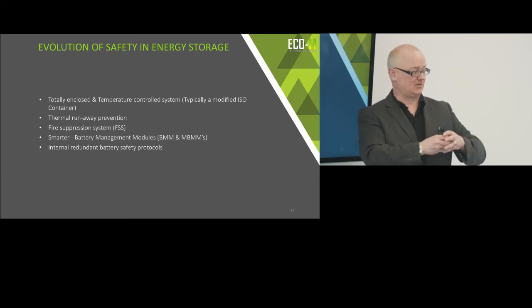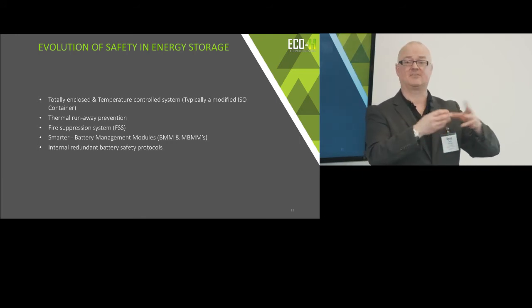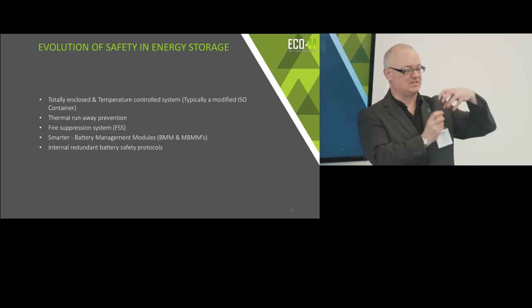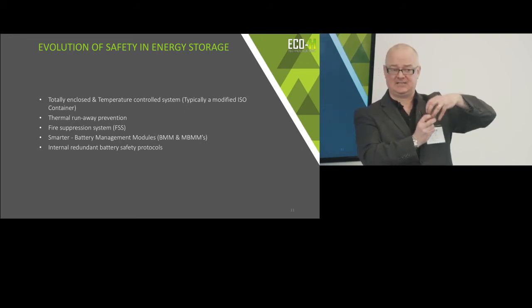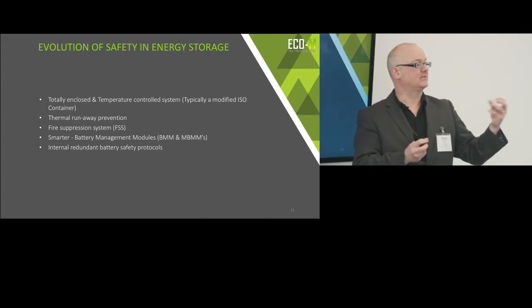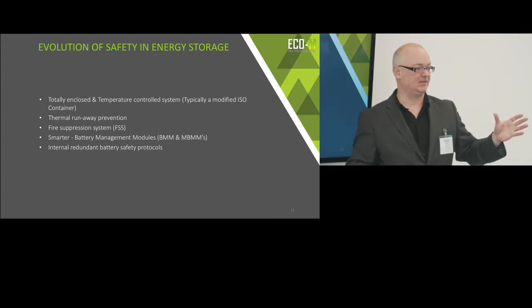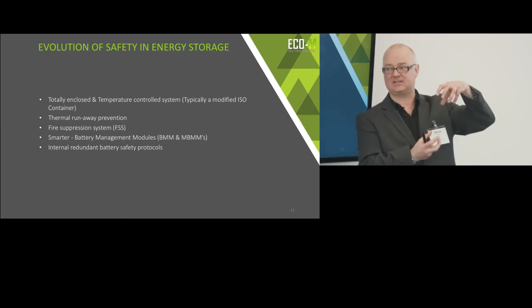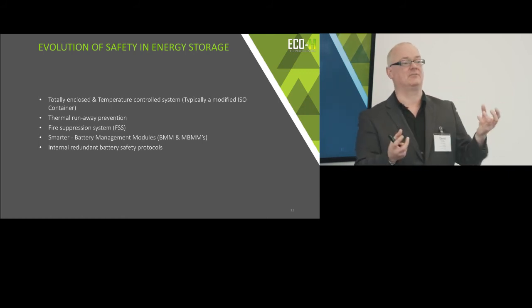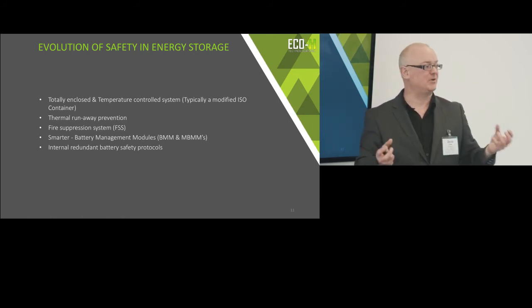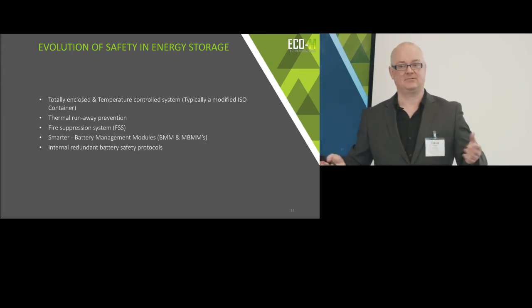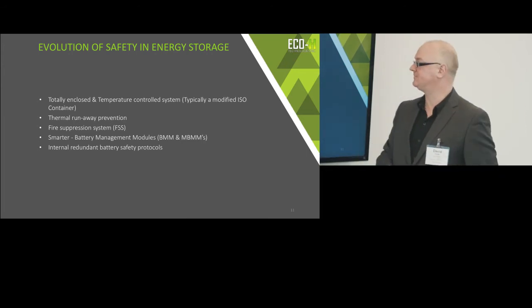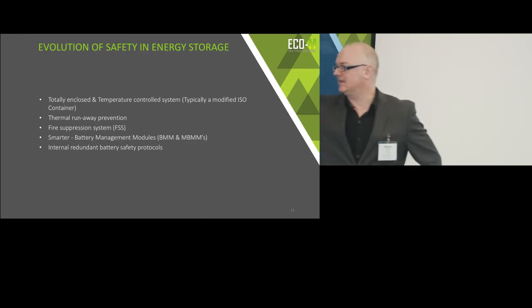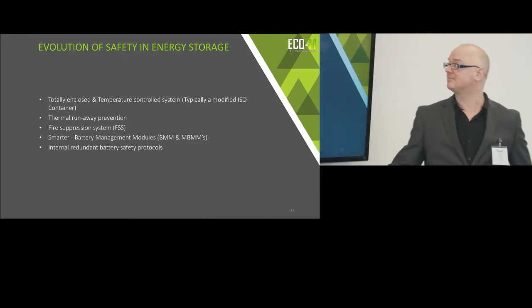Worst case scenario, a thermal event begins, and there's a cap on each cylinder with a weak point that physically breaks as it expands, stopping any current flow. It immediately breaks the circuit in that particular cylinder — a mechanical device — so it's physically impossible for current to flow, stopping the fault in that circuit. These are a lot of the internal redundant safety systems.